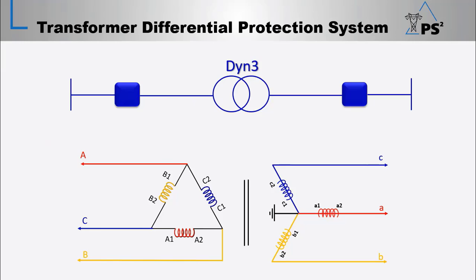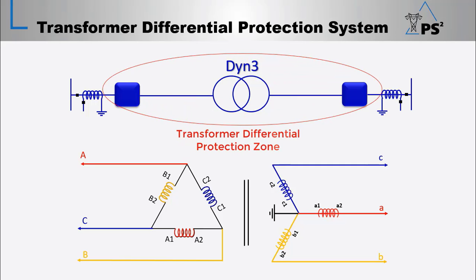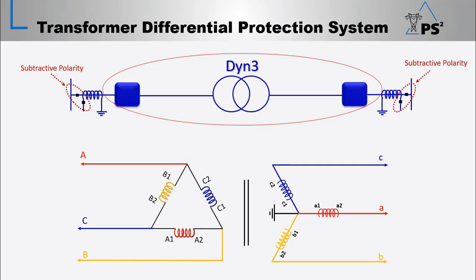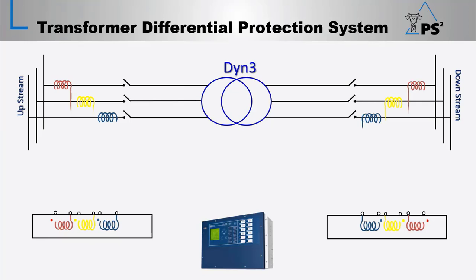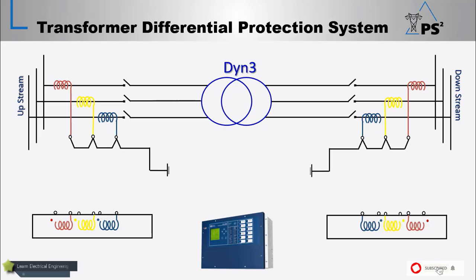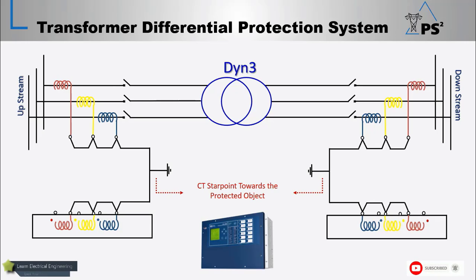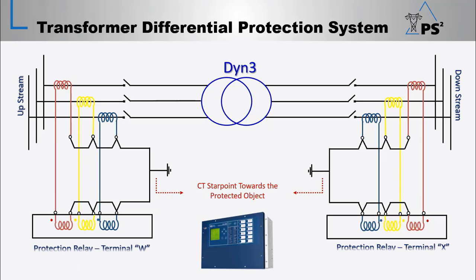Now to build the transformer differential protection system using numerical relays, we would place two current transformers on both sides of the transformer. And as we know, the zone of protection is determined and started from the CT location. Both current transformers will have subtractive polarity, and the CT star point will be towards the protected object. And this would be the three-phase CT wiring diagram where the CT star point is towards the protected object, which is the power transformer, and the CT terminals are W and X connected to the relay dot point.